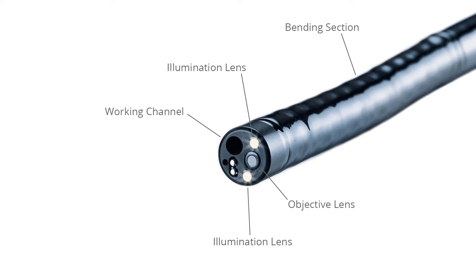The working channel is a lumen that allows endoscopic instruments to be inserted through the endoscope to perform procedures such as fine needle aspiration, FNA, drainage, injection, laser ablation, radio frequency ablation, biopsy, polypectomy, and electrosurgical coagulation and cutting. The gas, fluid, and suction nozzle lumen allows insufflation, irrigation, and suction to optimize access and visibility within the GI tract.